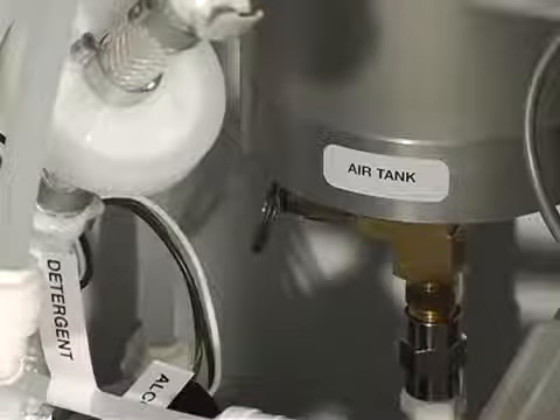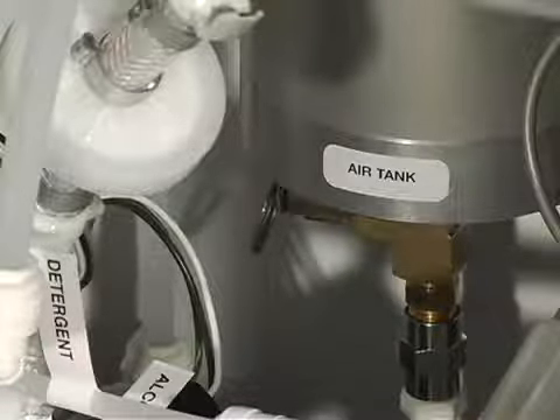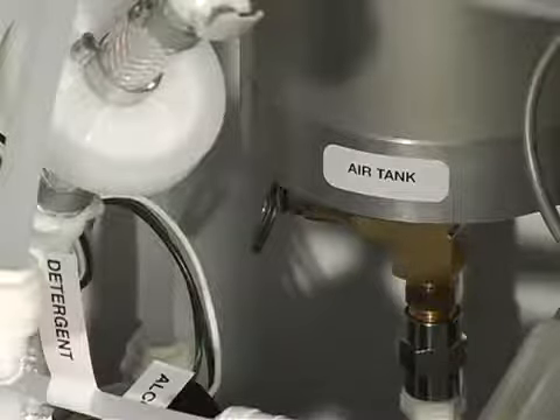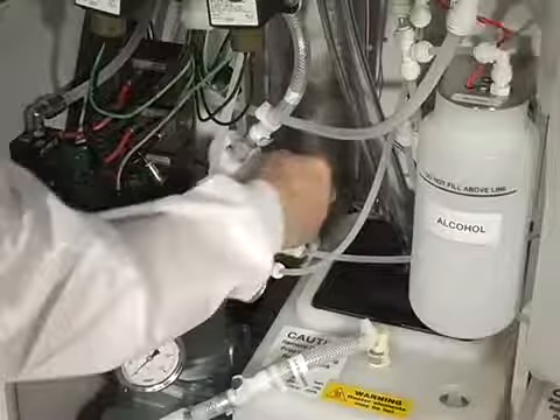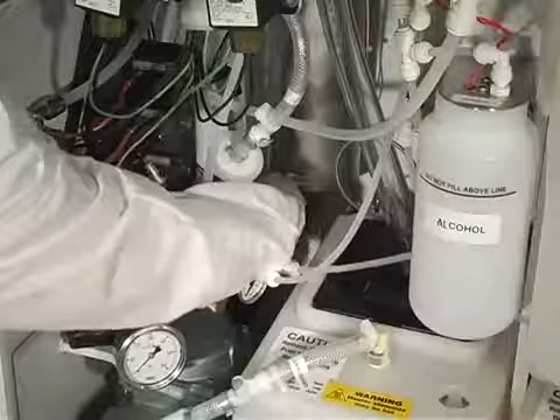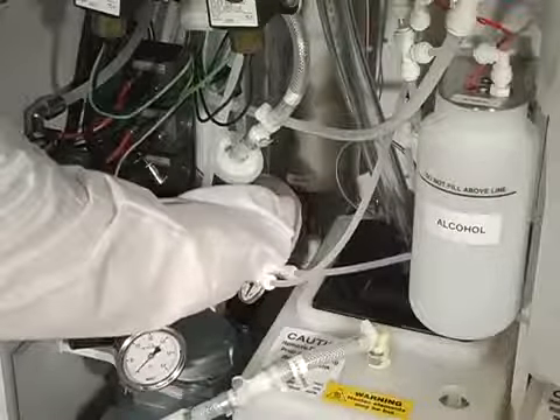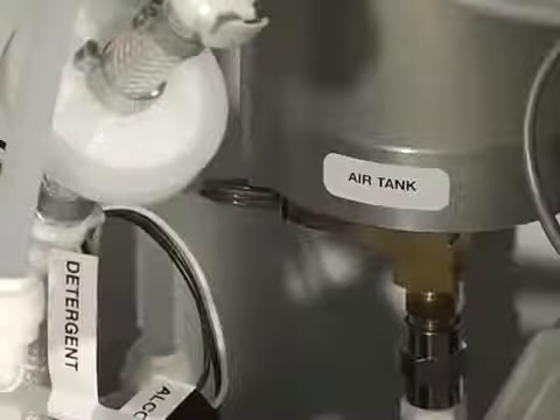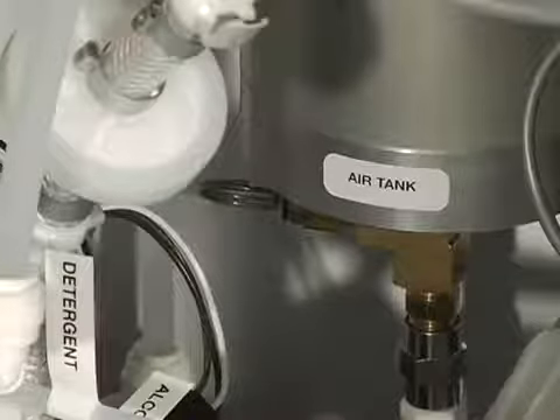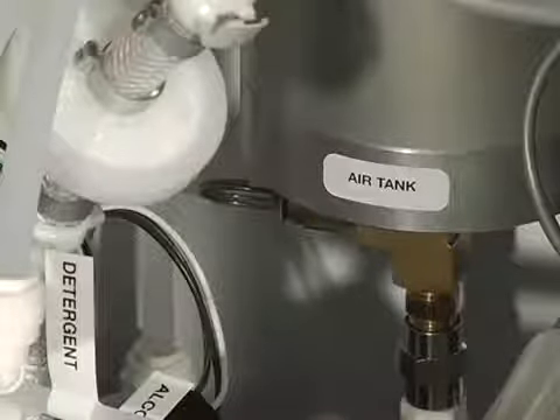In order to enhance the unit's cycle speed, it's equipped with an air tank. Condensation will naturally accumulate in the tank. It is recommended that it be drained at least once a month. This can be accomplished by simply locating the air tank in the back left side inside the cabinet between the reservoir and side A side panel. Pull the ring attached to the relief valve at the bottom of the air tank towards the left wall. Listen to hear or feel the purged air is free of condensation and release the ring back to its original position.